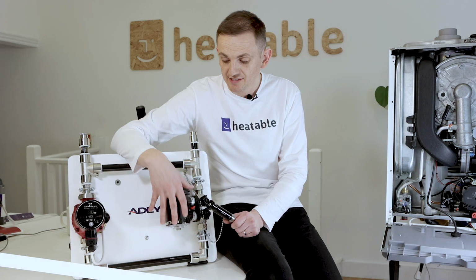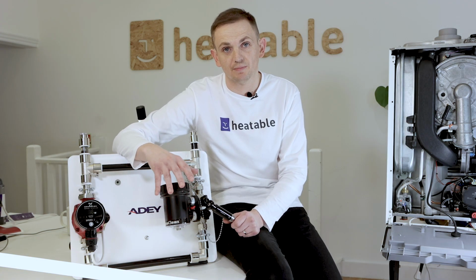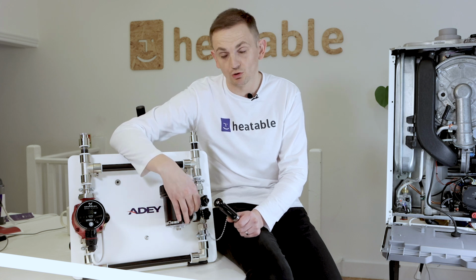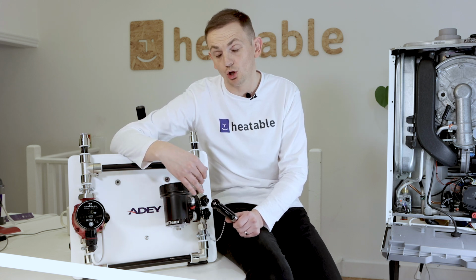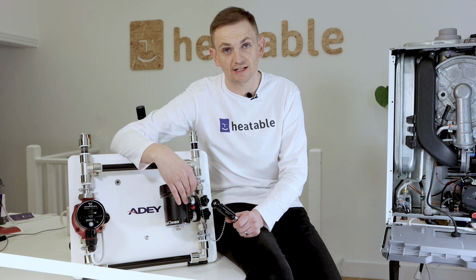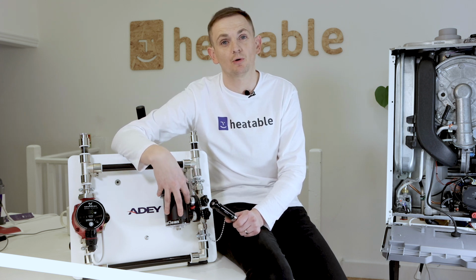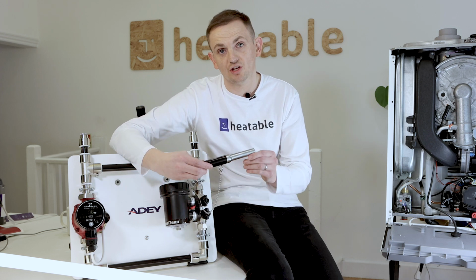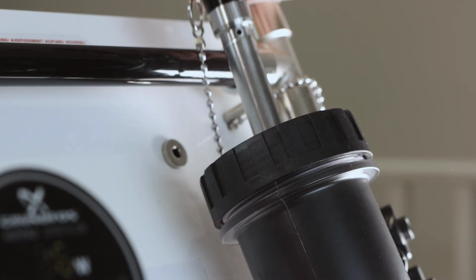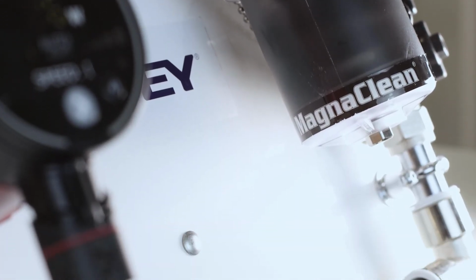Okay. This simulates no filter being installed on the system. So this water would enter the boiler, clog up the pipework, clog up the heat exchanger, clog up the diverter valve, and start to damage our boiler. When we insert the magnet back into the system, it only takes a couple of passes for the water to start to clear.